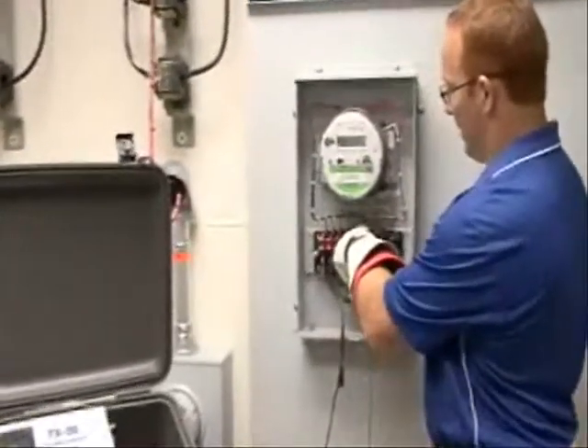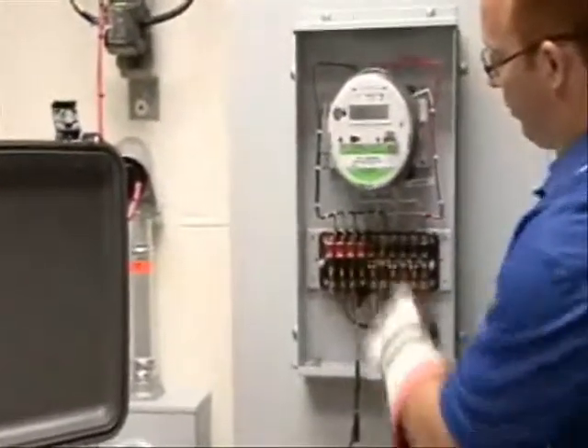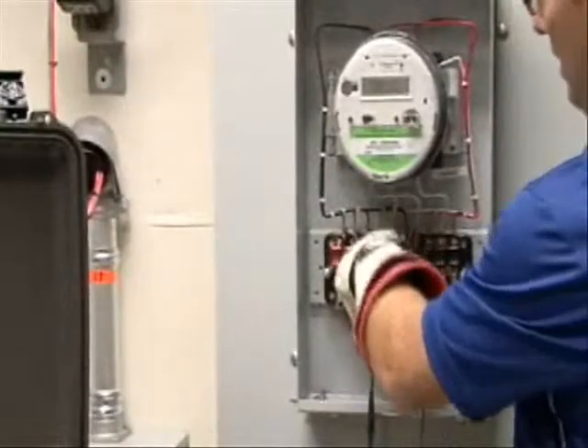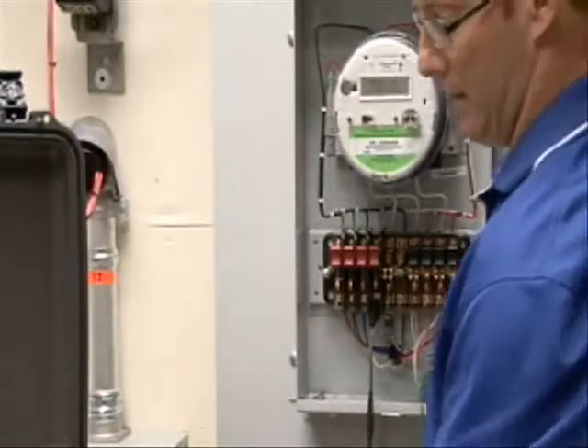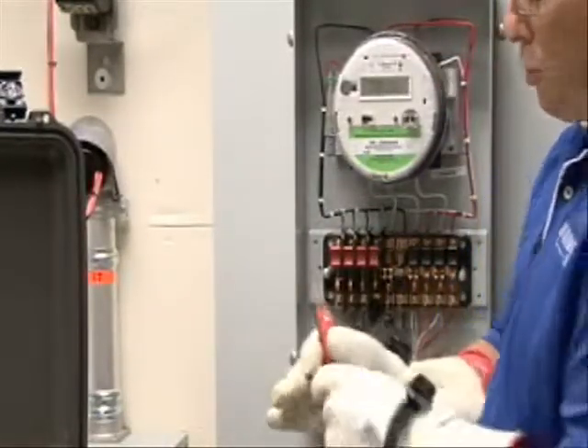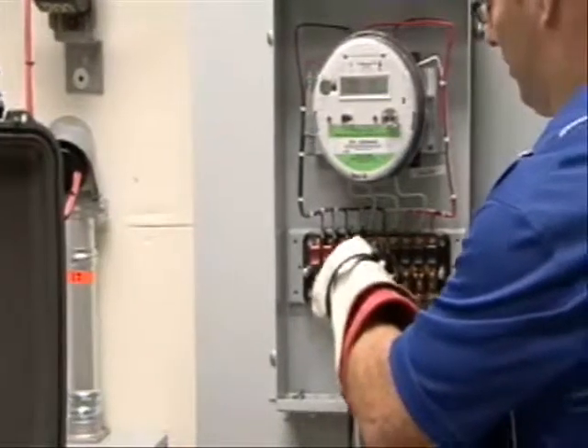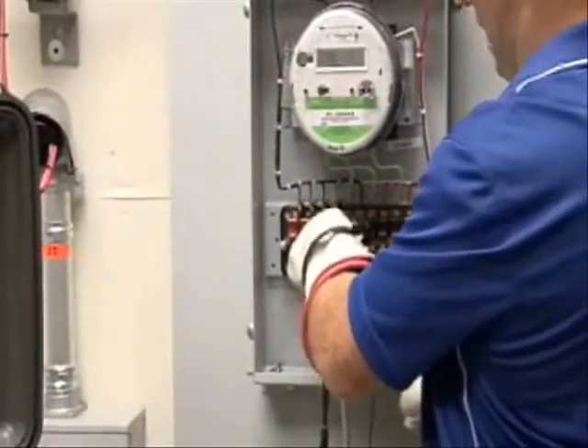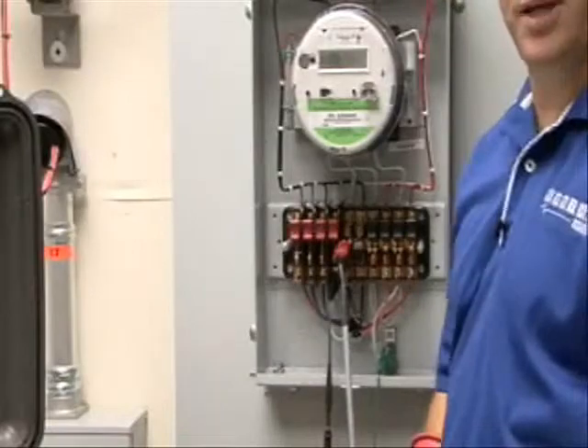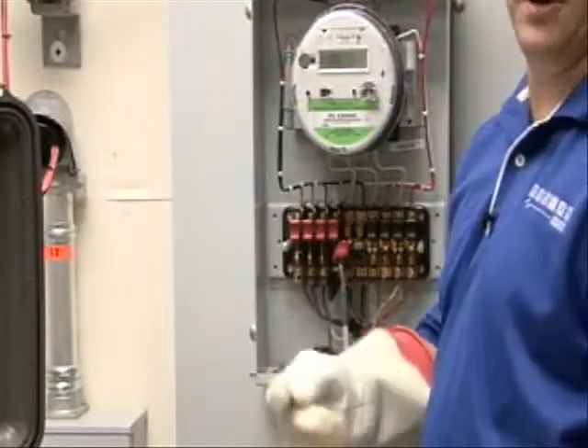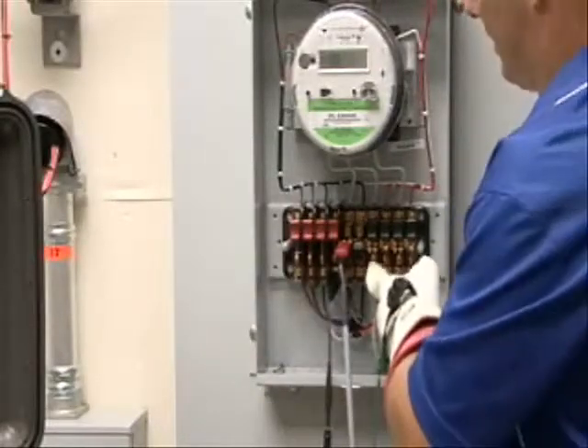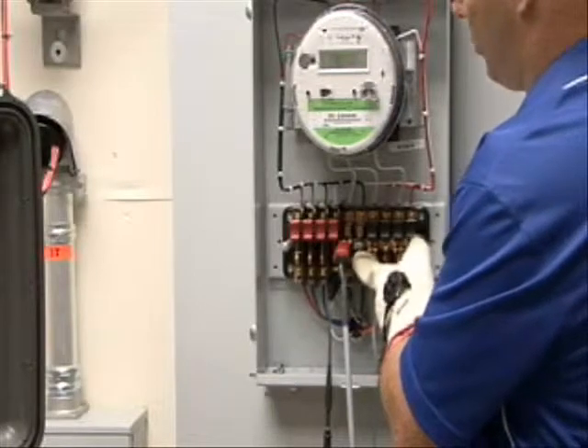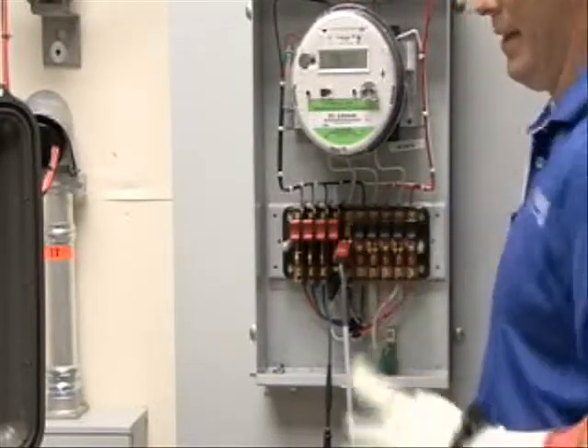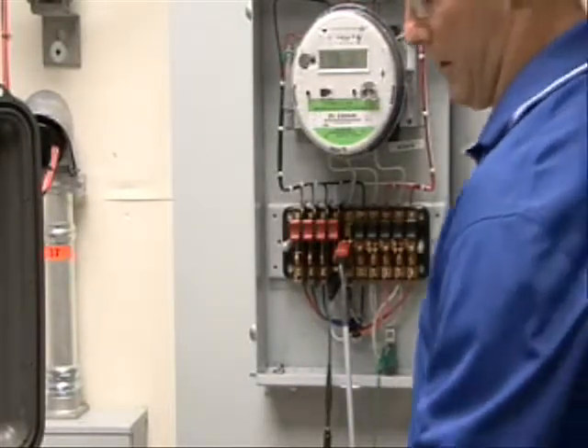And to do that, I'm going to use the test switch and throw the safety bypass, and then open up my test switch. Then I'm going to use my test switch probe and insert it in the test switch. I want to make sure not to insert it too deep, as it might cause a current return on the back side if it actually hits the back plate. And then I'm going to unshunt my CT so that the TX Auditor is going to be seeing the current.